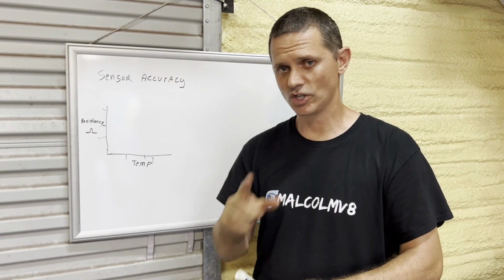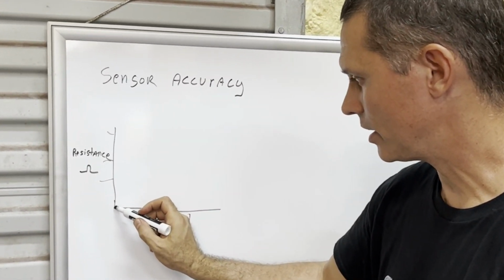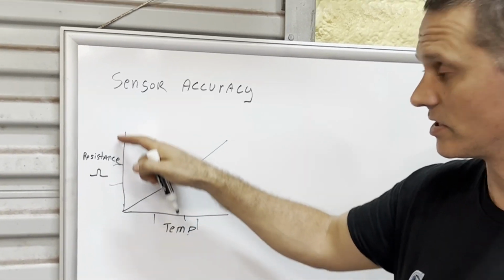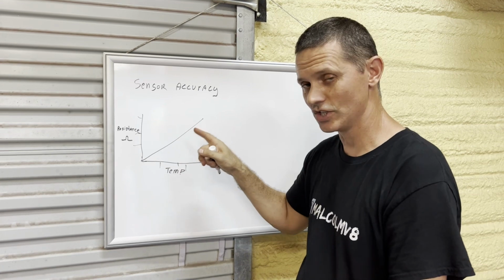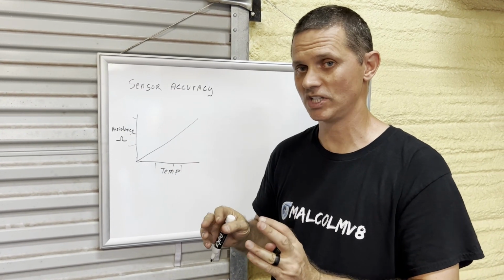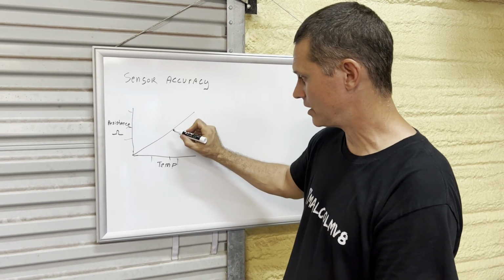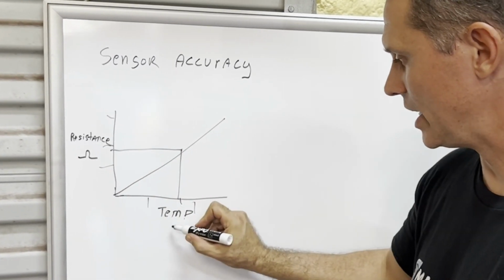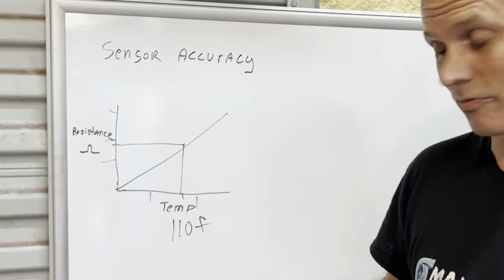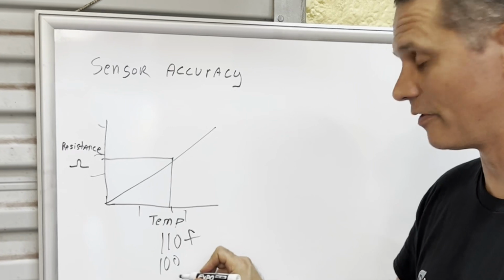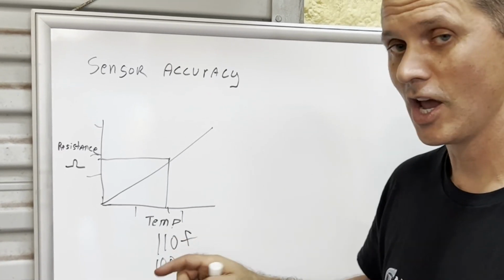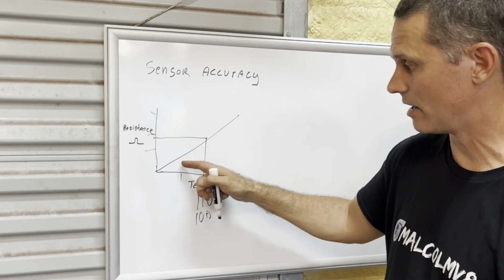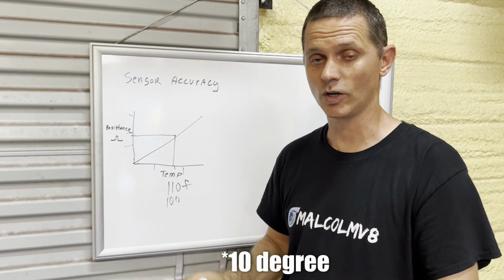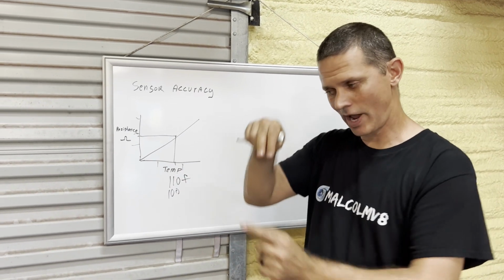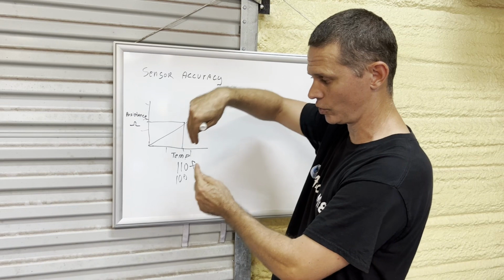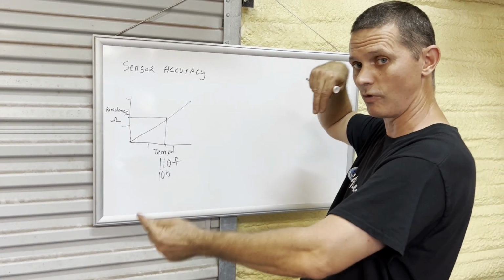And that gets a little bit complicated, and I just wanted to point out how I did that. If you plotted a line between temperature and the resistance of the sensor on a temperature sensor, it is not a linear line like this, unfortunately. That would make it so much easier. So if you wrote your code and said at a certain point you were reading 110 degrees on your sensor, but really the fluid was only 100 degrees, you could just put a 10-degree offset in your code to fix this. The problem is, as the temperature moves up and down, that 10-degree offset becomes invalid and incorrect, and your sensors start to read way out. If you have two sensors and you dial them in like that, as you cool them down and heat them up, the difference between them is going to move all over the place.